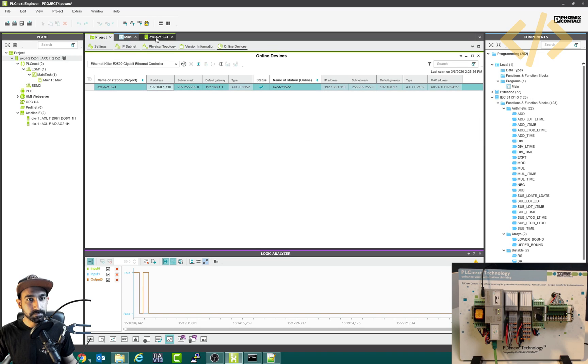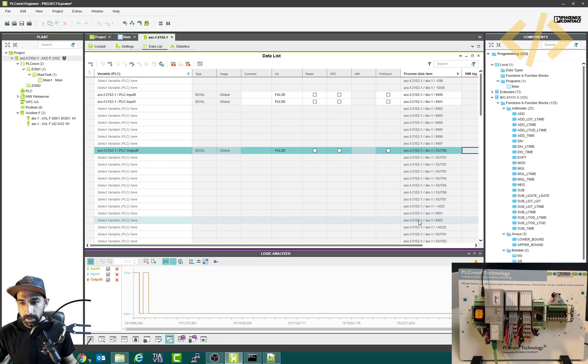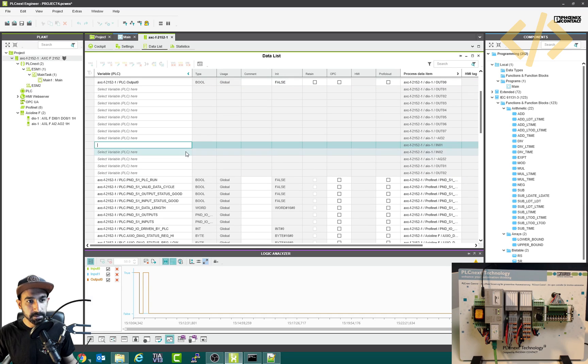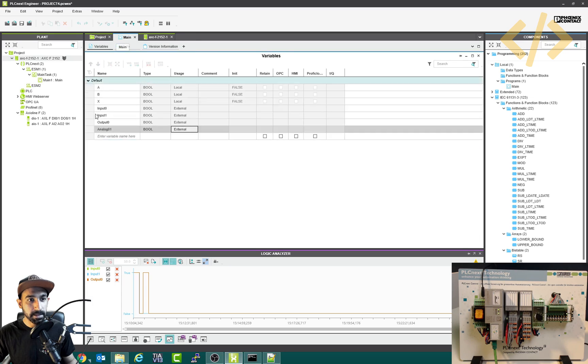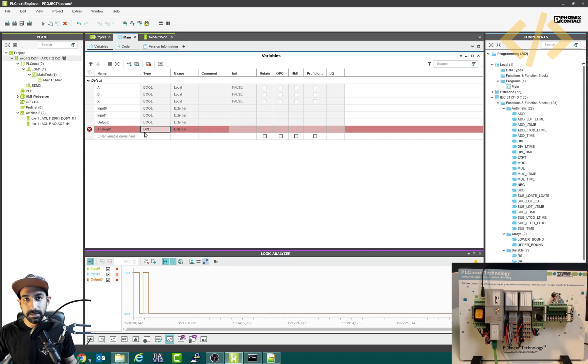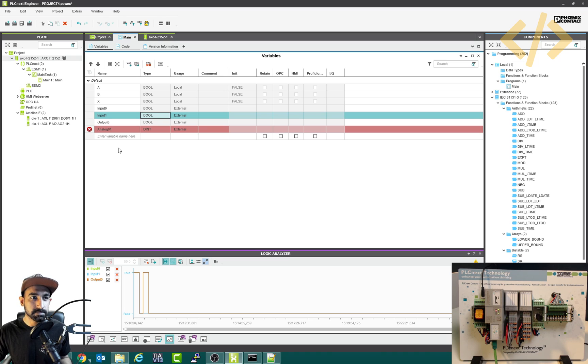Go to your controller properties and here you will find your analog input, which is aioin01, and define the PLC variable here. Before I define it, you can see it doesn't show anything — let me explain. Go back to your main. These analog IOs are not boolean; this is your analog input, so I will use double integer as the data type. We have different data types in PLC: boolean, integer, double integer, word, and float.